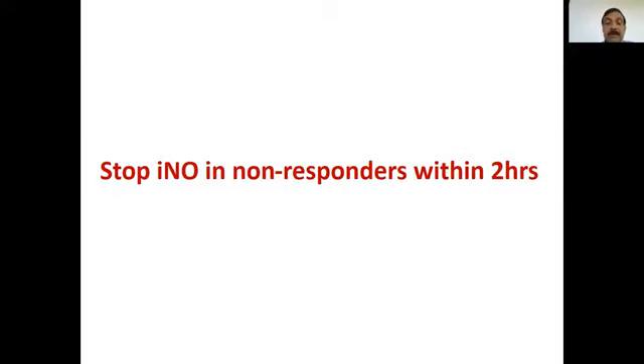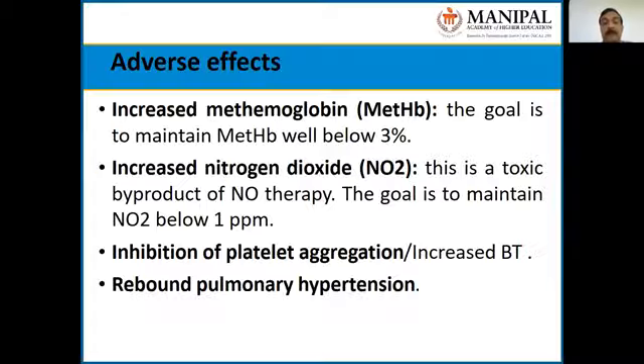So the message I want to convey here is, if we have not got an adequate response within a period of 2 to 4 hours, it tells us that possibly that particular baby with hypoxic respiratory failure is not going to respond to nitric oxide. Adverse effects: increased methemoglobin, which, as I mentioned, our target should be to keep less than 3%. The increased amount of nitrogen dioxide, which is a toxic byproduct, and the goal is to maintain below 1 parts per million.